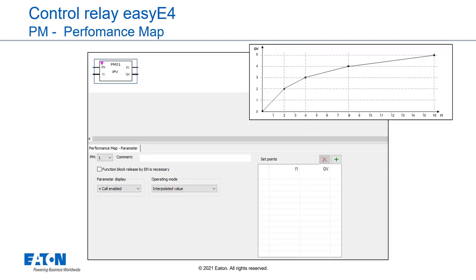easyE4 base devices provide four performance map function blocks. The performance map function block can be used to implement a characteristic curve function. This characteristic curve function is implemented by reading the value at function block input I1, looking up the corresponding output value in a reference value table and outputting this output value at function block output QV.